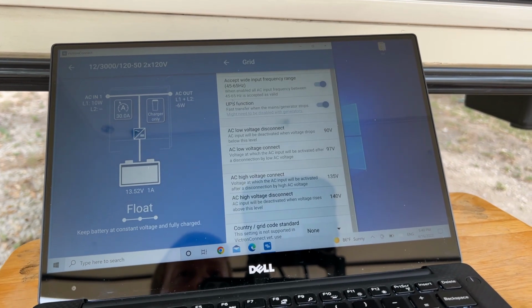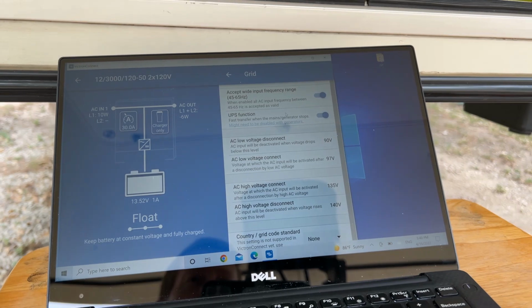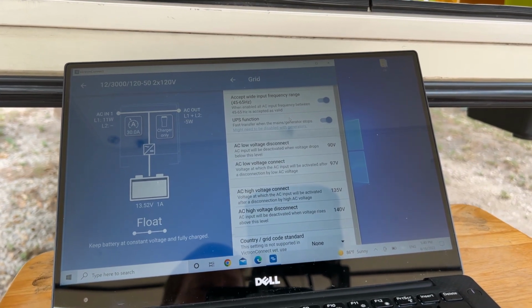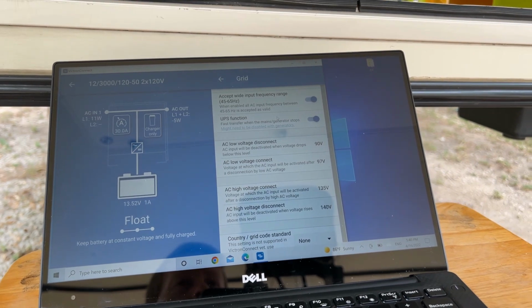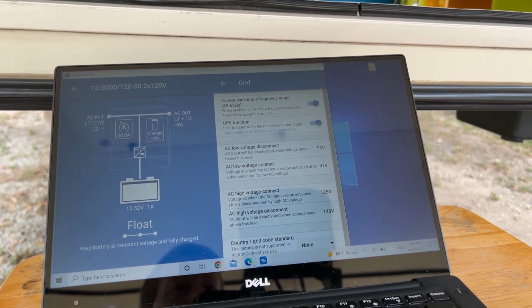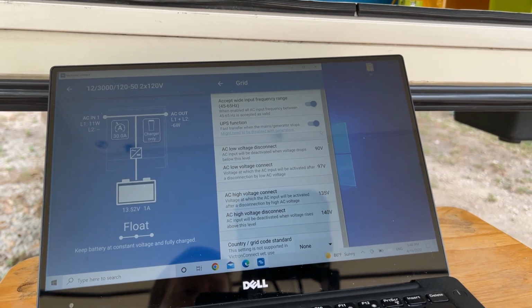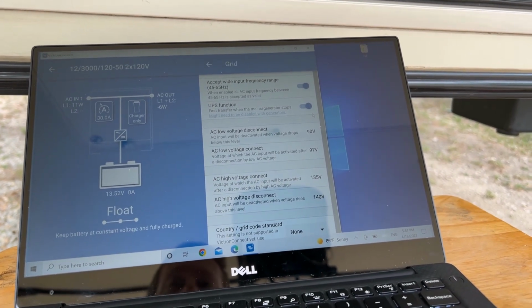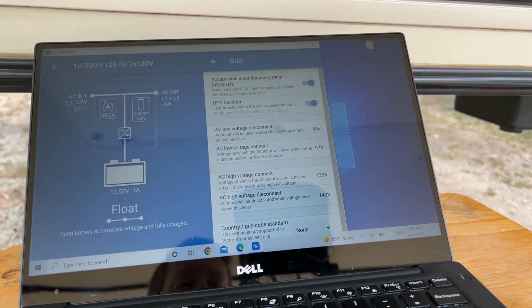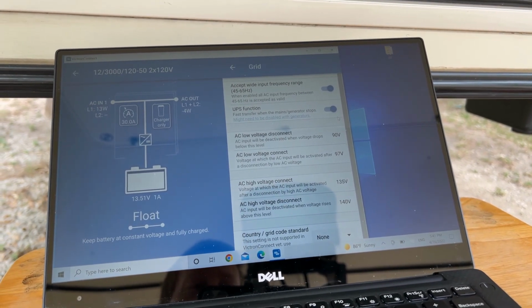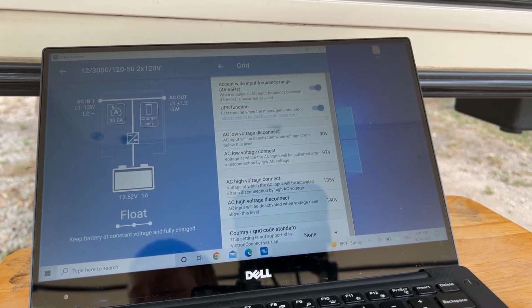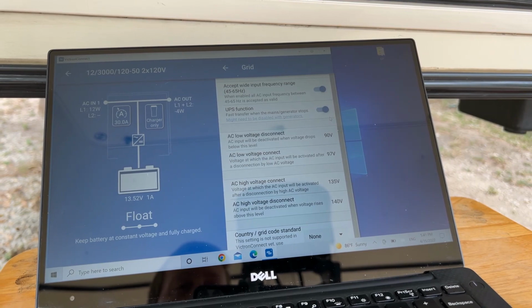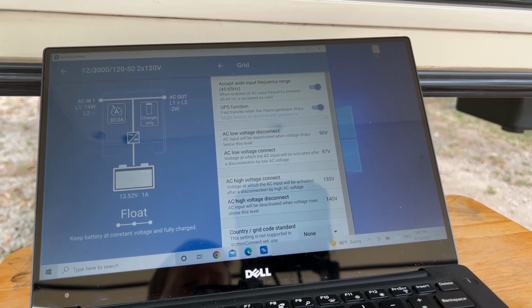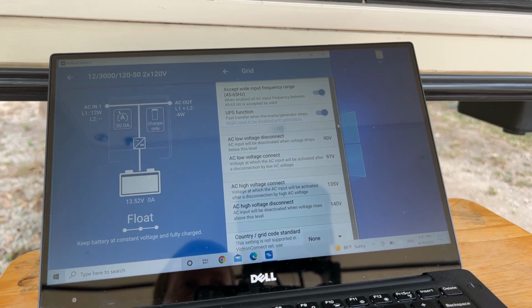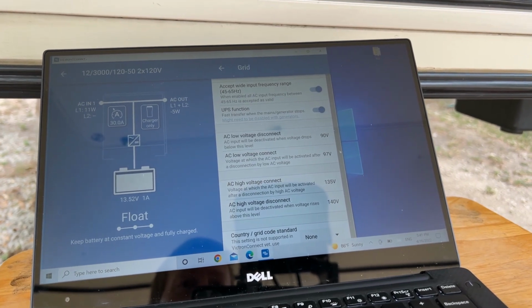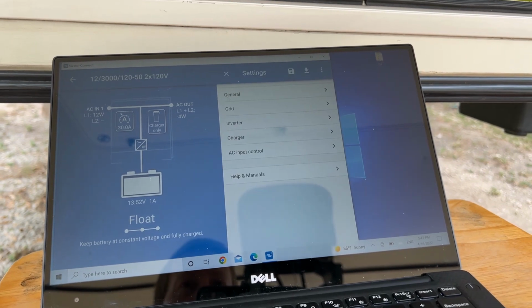All right, so the next thing, we go to grid. These are all pretty much default settings. I haven't really changed anything in here, as far as the frequency range of the power. UPS function, I believe that may have been turned off originally, but this basically allows your inverter to act like a battery backup system, like for your home PC, for example. If there is a disconnection of power, so if your campground loses power, it'll act like a UPS, so you don't have any interruption in power inside the RV. It's actually a pretty nice function. It switches very rapidly if there is a loss of power. All right, so those are the grid settings.